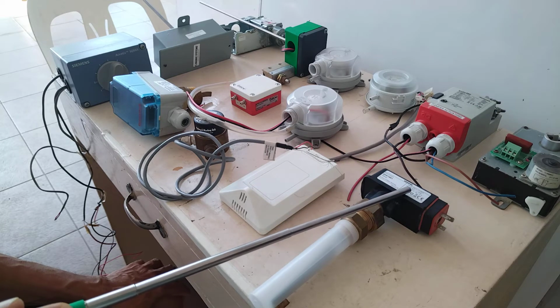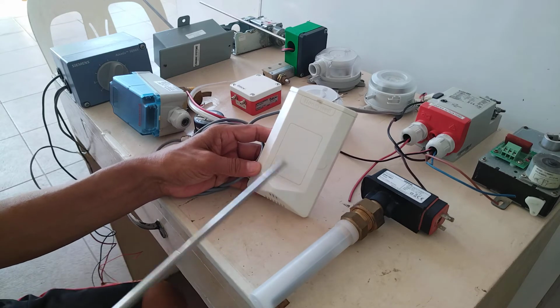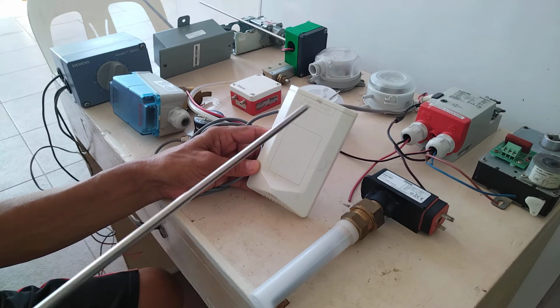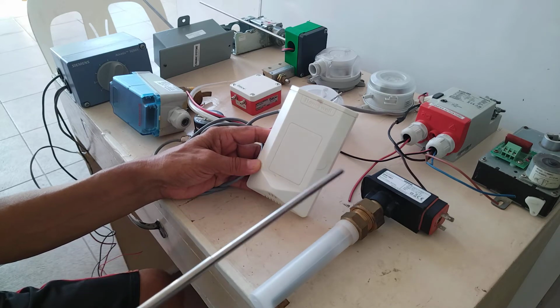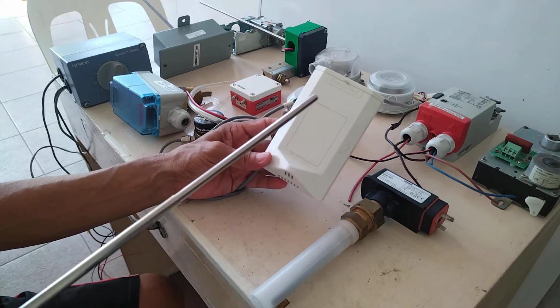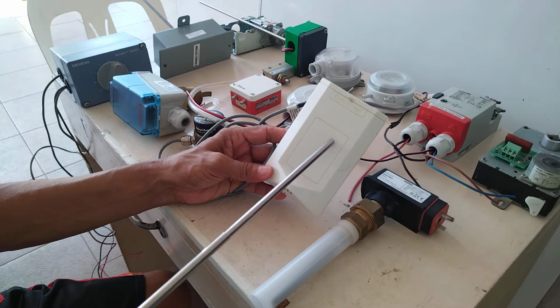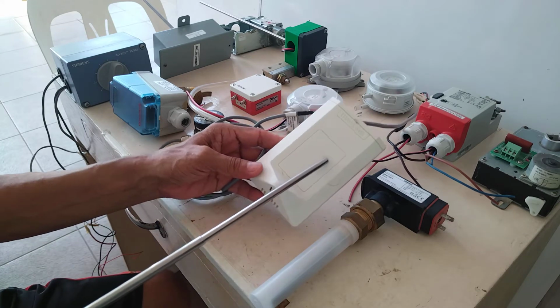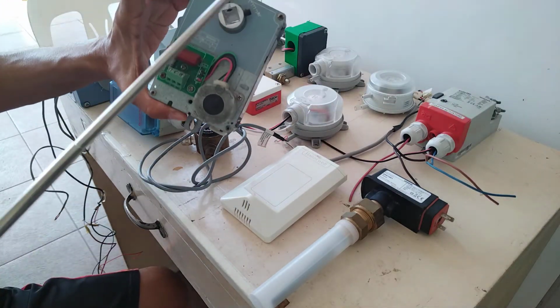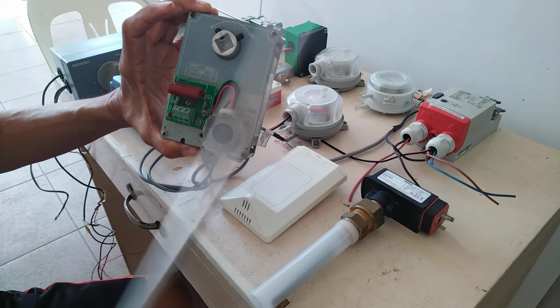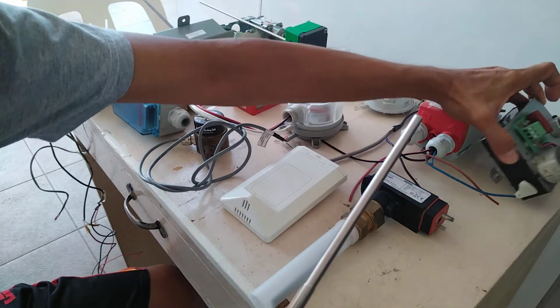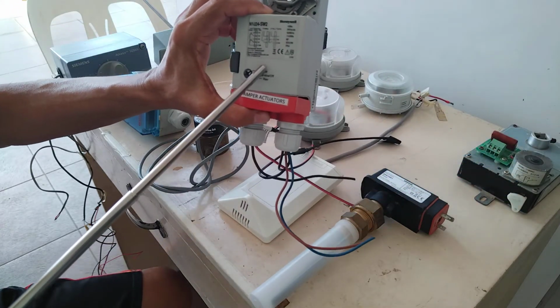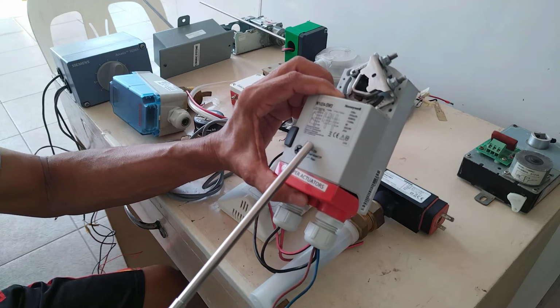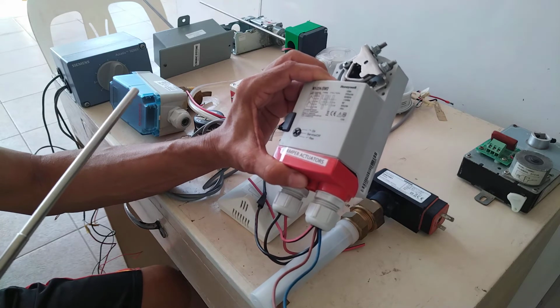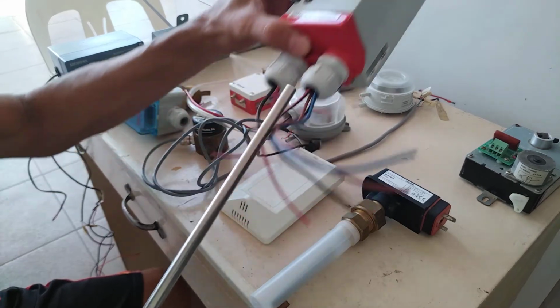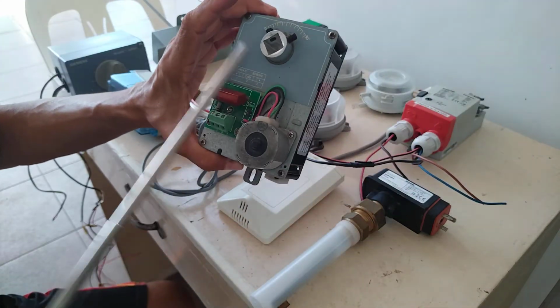Flow switch, water flow switch. Then this one is an ambient temperature and humidity sensor. Meaning this device, we are using for sensing the ambient condition. When we say ambient condition, it will tell us the outside air temperature and the humidity. Now I have here a damper actuator. I will explain later what the purpose is and how you are going to install it. Then I have another damper actuator, but this one is open and close, meaning it will open fully and close fully, opening at 100% then closing at 0%. This one is a modulating one, or 3-point control. I will explain that one later.